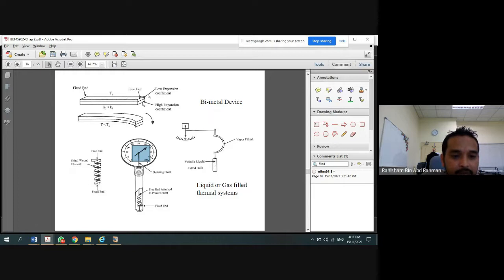Okay, so sometimes we will have this bimetal in the form of a spring, a spiral shape. The spiral is fixed into this gauge, and then we can actually see the pointer here, the difference, etc. Sometimes they are connected to a liquid or gas filled system. That means they don't use the bimetal device, but actually use liquid or gas. A very simple example for liquid, the easiest one, is what we find in the thermometer: mercury. We have mercury. Once it gets hot, it will expand and rise up to a certain value. And once it cools down, it will shrink and go to a certain value. As simple as that. Okay.